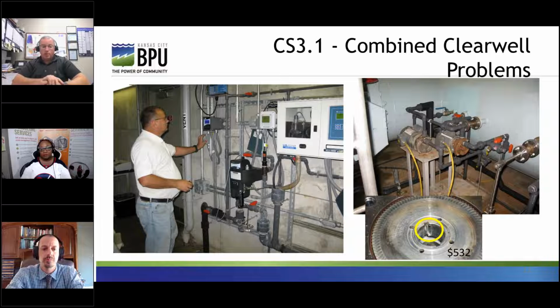1, a smaller 1/8 horsepower magnetically coupled pump capable of 26 feet of head at 18 gallons a minute for $434 new was installed. It's considered a run to failure with a spare always on the shelf. This pump doesn't like air either, but it's far more resilient than its turbine regenerative predecessor. 2, the source of aeration was confirmed using a technology that hadn't been previously considered, versus speculation. The technology is FASTIC, for detecting friction, impacting, and turbulence. I'll talk about that in the coming slides, where I'll show how we came up with a solution to the error and eliminated the problems.